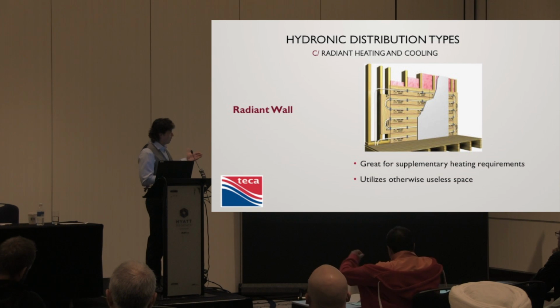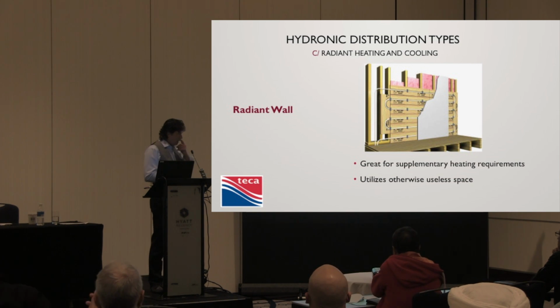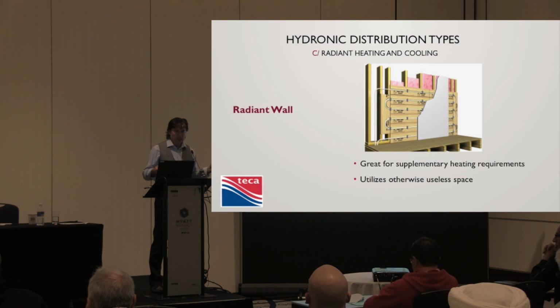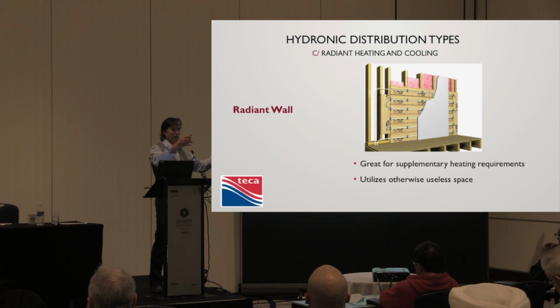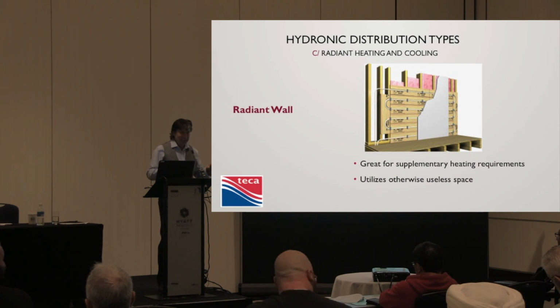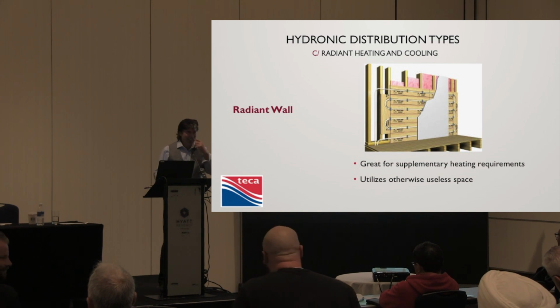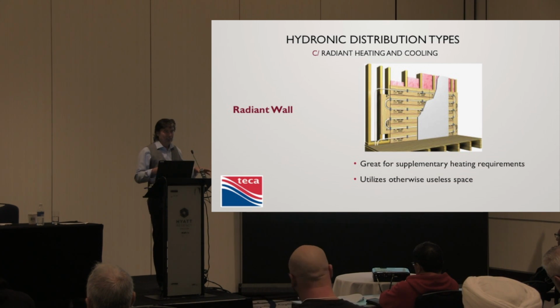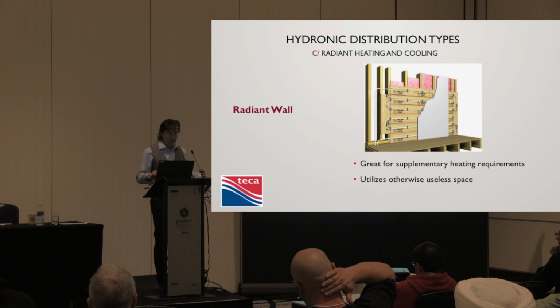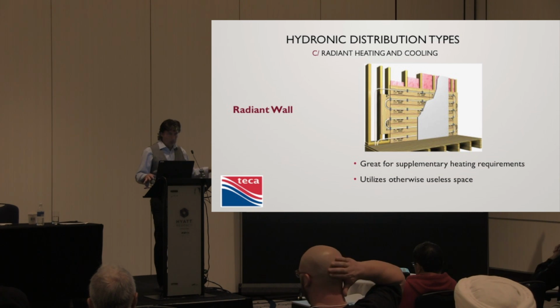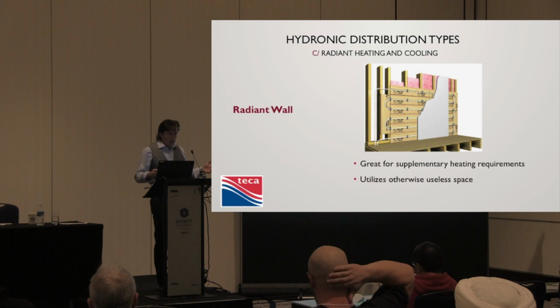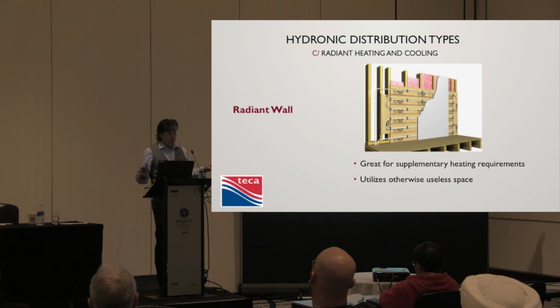So for supplementary heating requirements, let's say it is a solarium here. Let's say we've got glass, and I've got a nice tile radiant floor, some kind of nice tile there, and we really want to heat it with radiant floor. Of course, it's the best. But I have a limitation. I can get maybe 35 BTUs a square foot out of that radiant floor when it's smoking hot. I have surface limitations that I can't cross. We'll talk about that later. So I'm out of floor space. What am I going to do? I told you I don't want air in there.